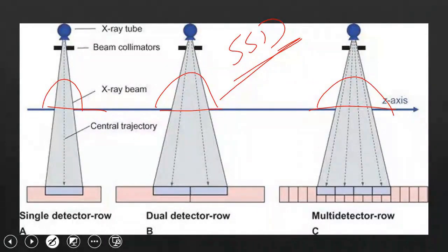Even if you are going to buy a machine, sometimes they will tell you they are selling a machine with 32 detectors or 16 detectors, but they might say that this device only has 8 rows of detectors. However, they claim to perform reconstruction with 32 detectors. So there are some aspects they play around with. It is very important for me to know this because it affects your control over the imaging process.